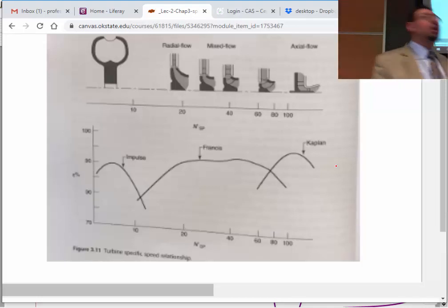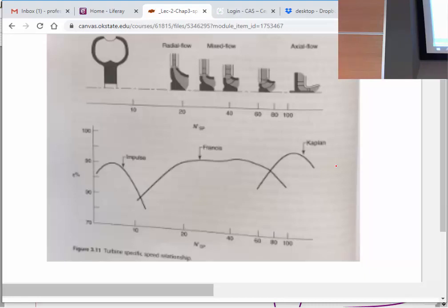It tells us that if our specific speed, if you remember from Fluids one, this combination of flow rate, head, and the RPM that we are rotating with, ends up here, it would not be smart to use anything but an axial machine, because if I use a radial machine, the efficiency will drop at that place. And if I'm going to operate here, it's not really smart to use a Pelton wheel, because the Pelton wheel efficiency will drop so much.